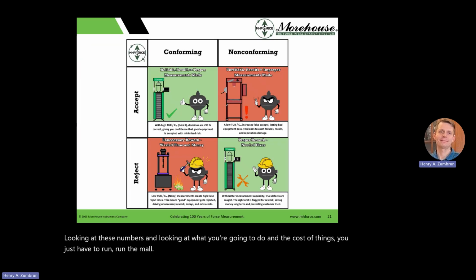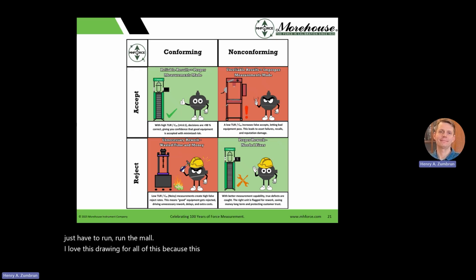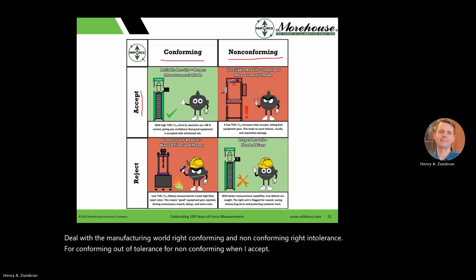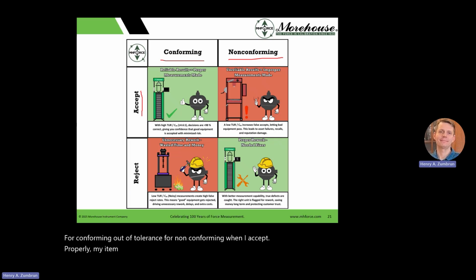I love this drawing for all of this because it shows everything, right? We deal with the manufacturing world: conforming and non-conforming, in tolerance for conforming, out of tolerance for non-conforming. When I accept properly, my item is conforming and I accept it properly with a high TUR of greater than 4.6 to 1. Decisions are greater than 98% correct, giving you confidence that good equipment is accepted with minimal risk. On the other side, when it's non-conforming, a low TUR increases false accepts, letting bad equipment pass. This leads to asset failures, recalls, and reputation damage. This is what almost everybody tries to avoid at all cost, right?